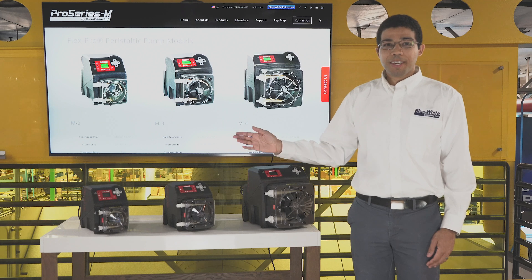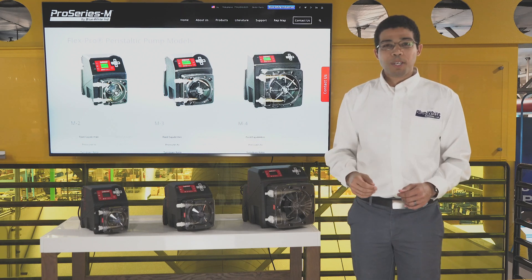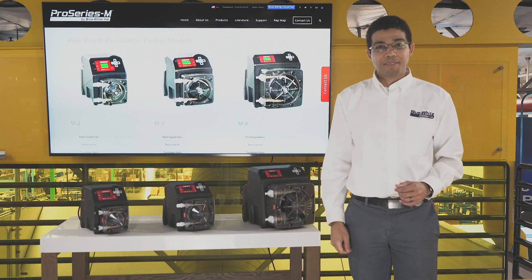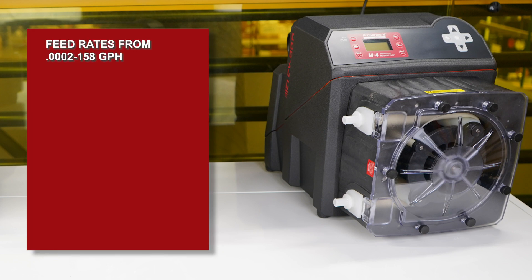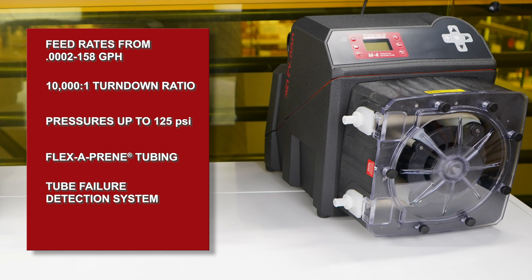The M2, M3, and M4 FlexPro peristaltic metering pumps were specifically designed for municipal water treatment applications. These skid-ready pumps have feed rates from .0002 to 158 gallons per hour, a 10,000 to 1 turndown ratio, discharge pressures to 125 psi, chemical-resistant pump tubes including our patented Flex-A-Prene tubing, a patented tube failure detection system, and a five-year warranty.